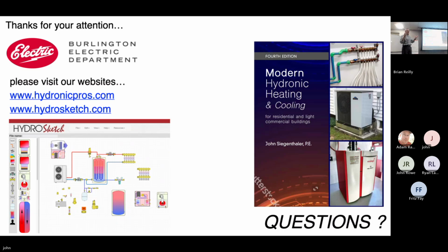So that's where I feel the manufacturers need to go for support. They need to create, again, 15 to 20 templates that cover 90% of the common situations. There will always be the one-up custom house. They want the pool heated, they want the snow melted, they want the space heat, all this stuff. And hydronics can do that, and I've made a living doing design on projects like that. But it falls between the cracks because the manufacturers don't want the design liability, which you can understand. The wholesalers usually don't want it either. They will guide you, and some of the better wholesalers might have some templates. But I've also seen really bad advice coming out of some wholesalers, like staple the PEX to the bottom of the subfloor, no plates, that kind of stuff.